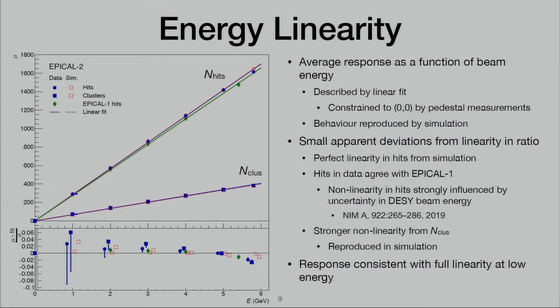Also shown here are in fact the results from our earlier prototype, which is a similar principle, but uses a different silicon sensor, the Mimosa sensor, which is much slower, and we had much more noise and problems with that at that point. But the absolute value of the number of hits is very, very close without any intercalibration between the two. So that's what you really get.